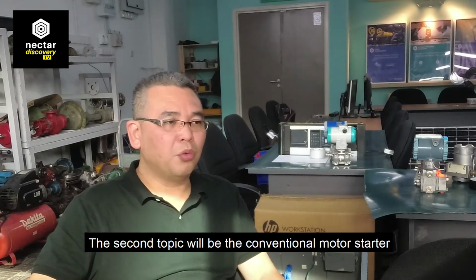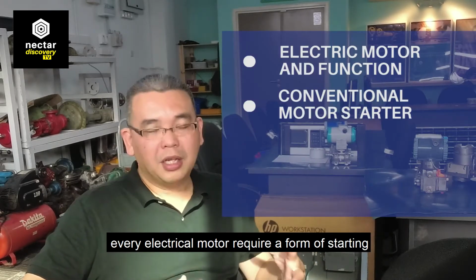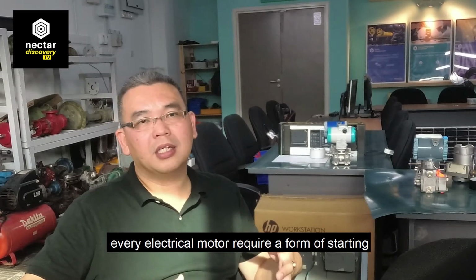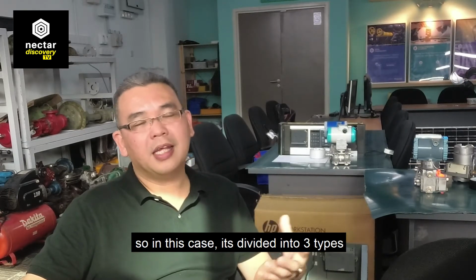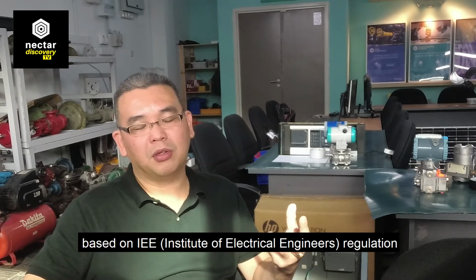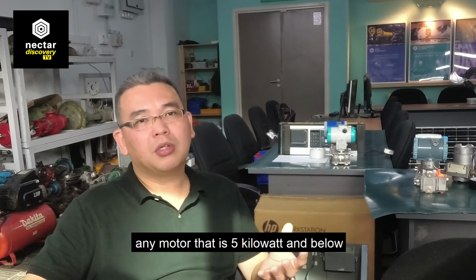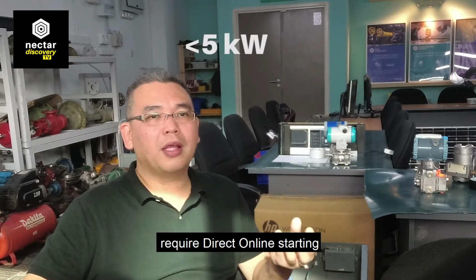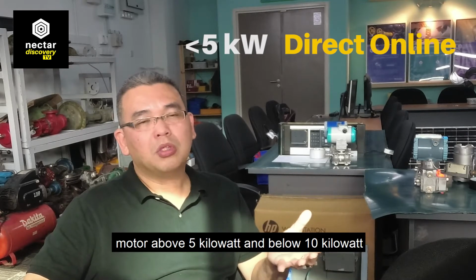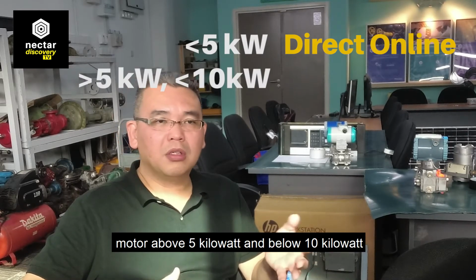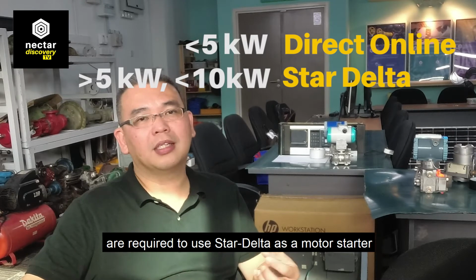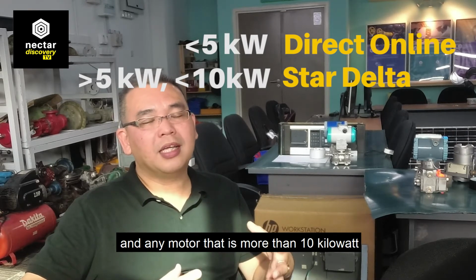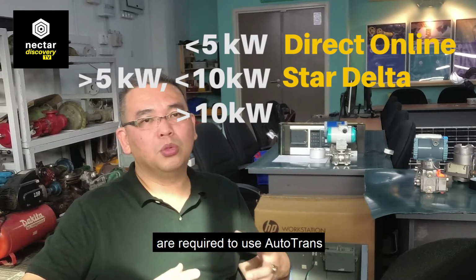The second topic will be the conventional motor starter. Every electrical motor requires a form of starting. In this case, it is divided into 3 types based on IEE regulation. Any motor that is 5 kilowatt and below requires direct online starting. Motors above 5 kilowatt and below 10 kilowatt are required to use star delta as a motor starter, and any motor rated more than 10 kilowatt is required to use auto transformer starting.